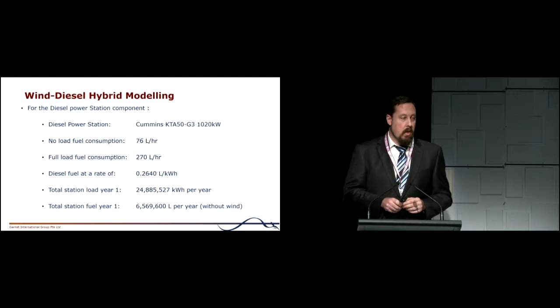Once we start to integrate some of the wind turbine modelling into this, we use the energy output based on the software, and we used an averaged demand from the site, and initial investigations came out with a calculated wind penetration, just wind diesel hybrid alone, of 56%. So this results in the fuel load for the power station in year one reducing to a little over 4 million litres per year. So it's a difference between the no wind case and the wind case of 2.5 million litres of diesel per year. It's a 38% reduction in diesel consumption in year one.